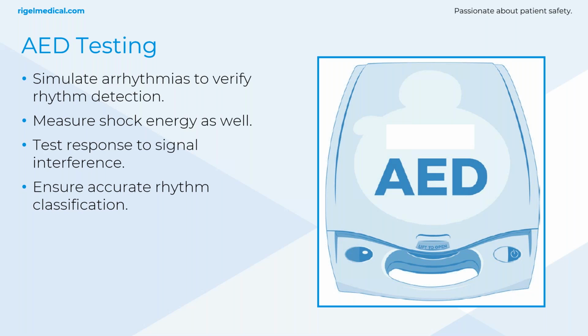What the defib needs to do is filter out any noise that it sees on mains frequency, so 50 or 60 hertz, depending on where you are, is imposed onto the ECG signal. And what the AED or defib needs to do is recognize that interference and filter out those 50 or 60 hertz signals, and only recognize the ECG arrhythmia.